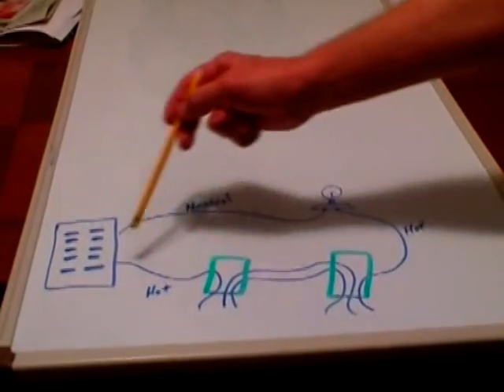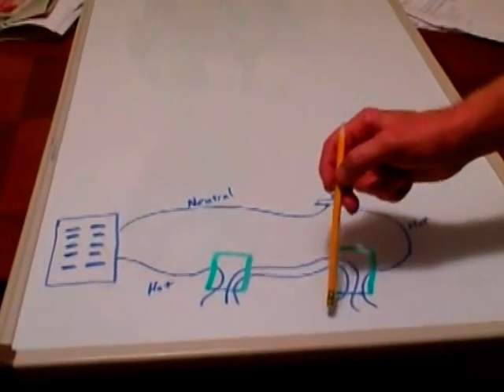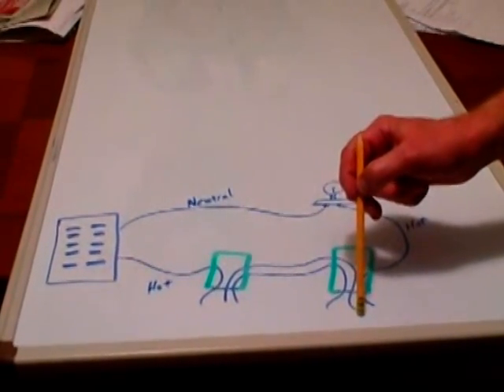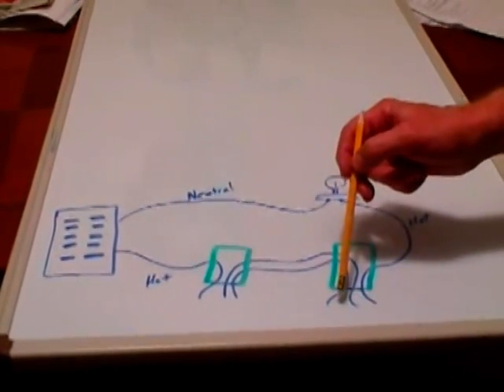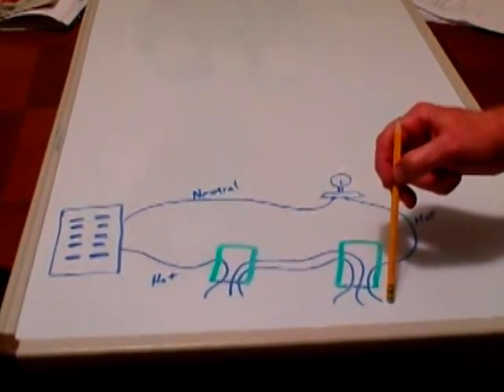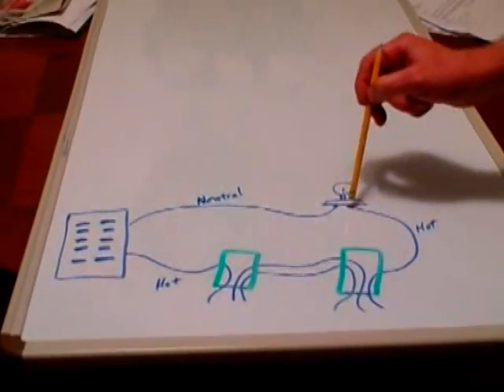Now we're going to go back and shut off the electric again and wire our second three-way switch. The two lines that we identified as hot are our travelers. We'll connect those to the light colored screws and we know that this last wire that wasn't hot is going to be the common dark colored screw going up to the light.